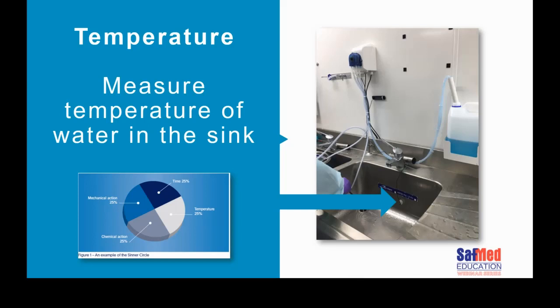Detergent efficacy can be affected by the water temperature. If the water is too cold, it'll be less effective. If the water is too hot, and you're using an enzymatic-based detergent, the enzymes may be rendered ineffective.